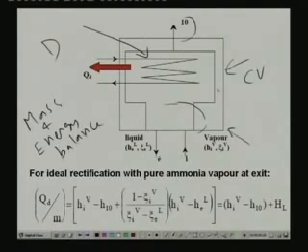For this control volume you can arrive at this expression: Qd by m dot. Qd is the heat rejected in the dephlegmator divided by m dot. m dot is the refrigerant flow rate from the system. So, Qd by m dot is equal to HIV, the vapor enthalpy at any cross section, minus H10, the enthalpy of the refrigerant vapor leaving this section, plus (1 minus zeta IV) divided by (zeta IV minus zeta EL) into (HIV minus HEL).